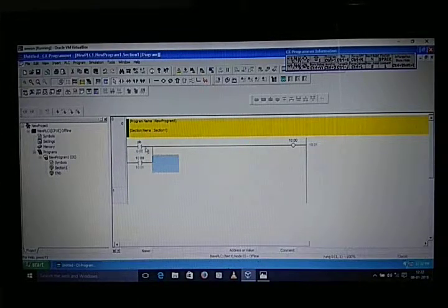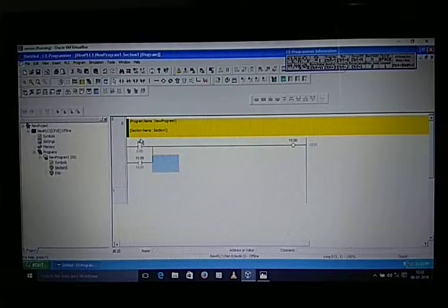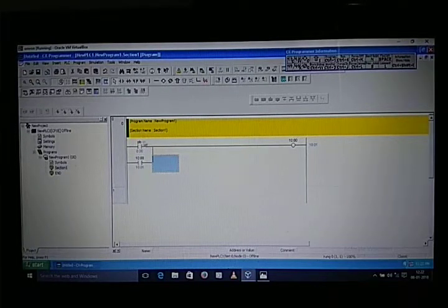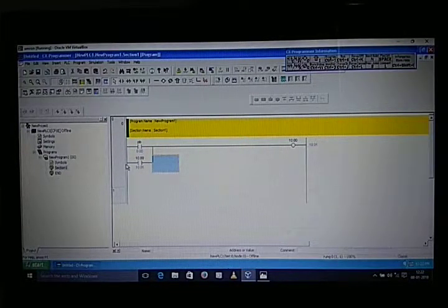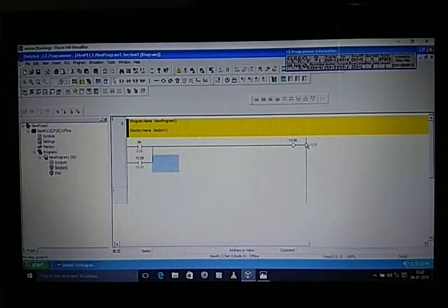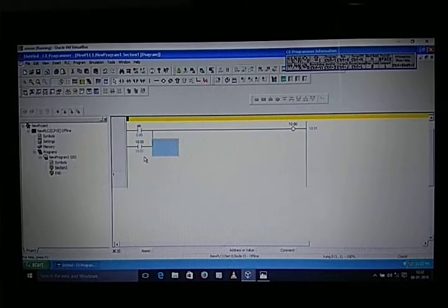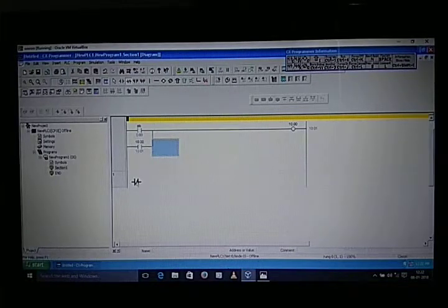When we push the button it will become NC and the output will turn on, but since this is a push button we have to release it. When we release the push button it will remain on because we are doing latching — when the output is on, that NO contact becomes NC and the output remains on. It's like a DOL starter.